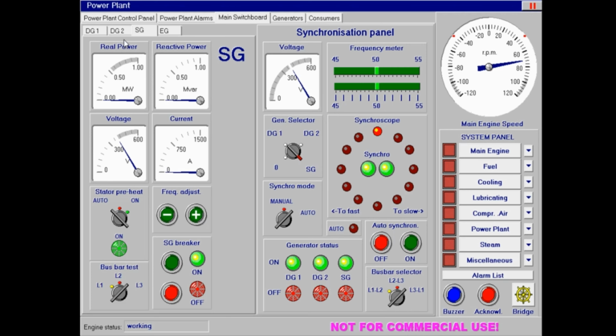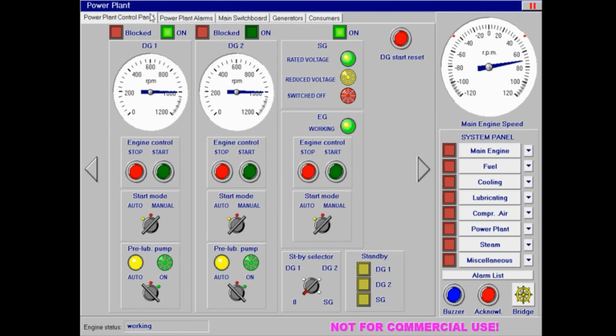Don't need this much electricity generating, so I'm going to go to diesel generator 2, and I'm actually going to disengage it. When you take a generator offline, you have to take it offline gently, so I'm going to use that auto synchronizer again to pull it off, which is easy. So to power plant control panel. Normally you let the diesel shut down and gently cool off, but I'm a cheater, so go ahead and stop. After doing that, I'm going to come down where it's start mode, set that to automatic. I'm going to stand by to see if something bad happens, which with me almost always does.